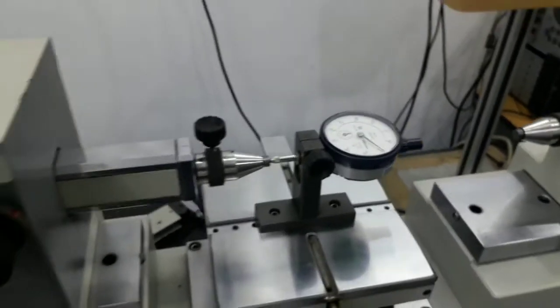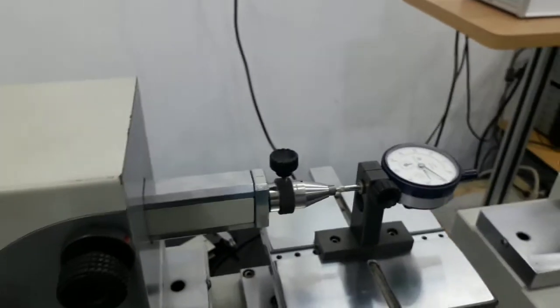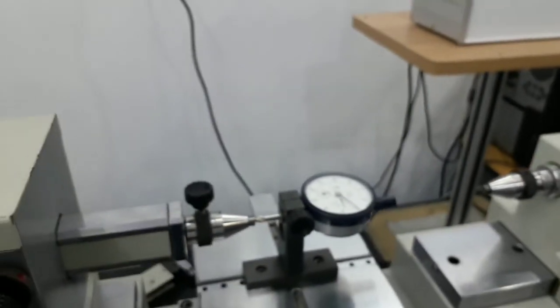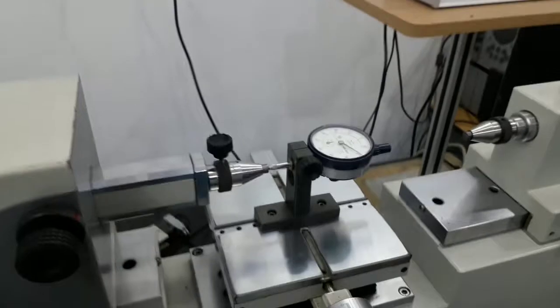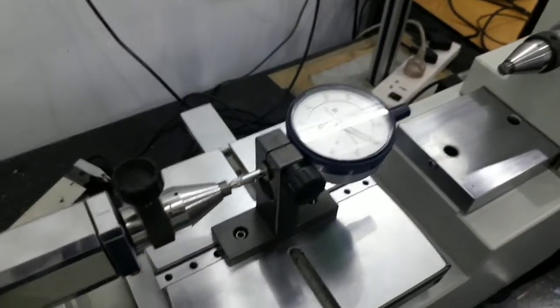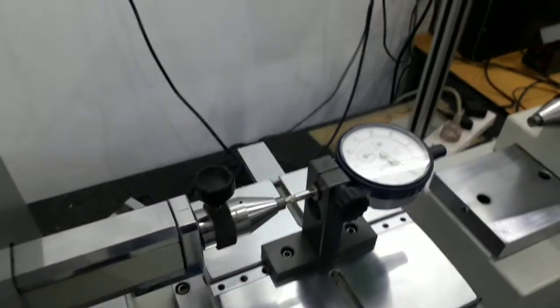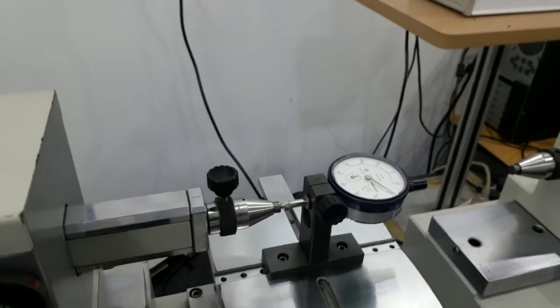This way we calibrate the dial gauges for its entire range, and the error registered is given in the report. This is how the plunger dial gauge is calibrated. In the same way, in the same position we can mount a lever dial gauge and bore dial gauge, and the calibration can be done using a ULM.